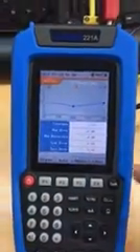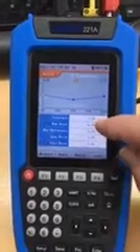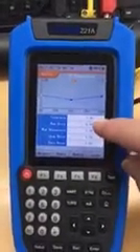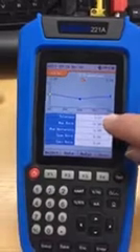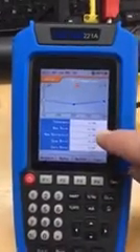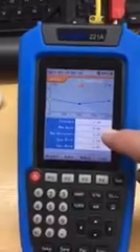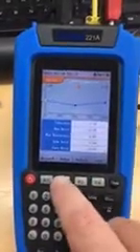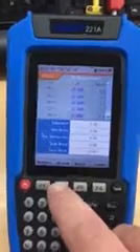to tell us that we set an acceptable error of 1%. Sorry, in this case we set a tolerance of 3%, so it's actually okay. The maximum error was minus 0.9%, and in fact you'd even look at the individual data if you wanted to see the results of the source, current and results.